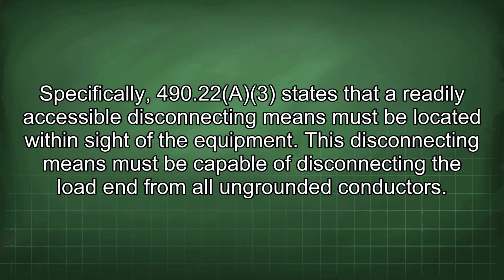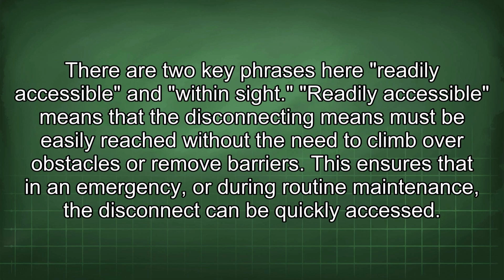Specifically, 490.22(A)(3) states that a readily accessible disconnecting means must be located within sight of the equipment. This disconnecting means must be capable of disconnecting the load end from all ungrounded conductors. There are two key phrases here: readily accessible and within sight. Readily accessible means that the disconnecting means must be easily reached without the need to climb over obstacles or remove barriers. This ensures that in an emergency or during routine maintenance, the disconnect can be quickly accessed.